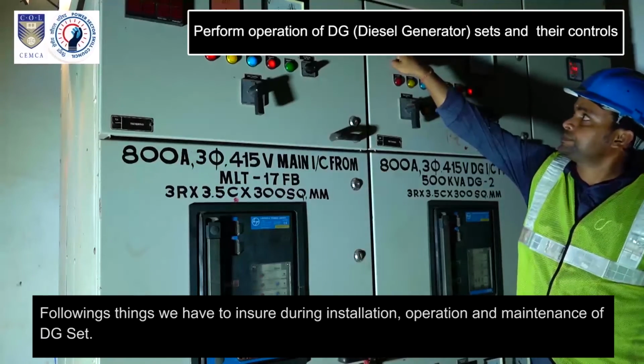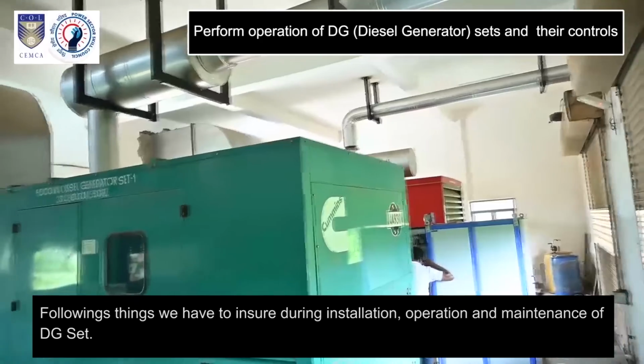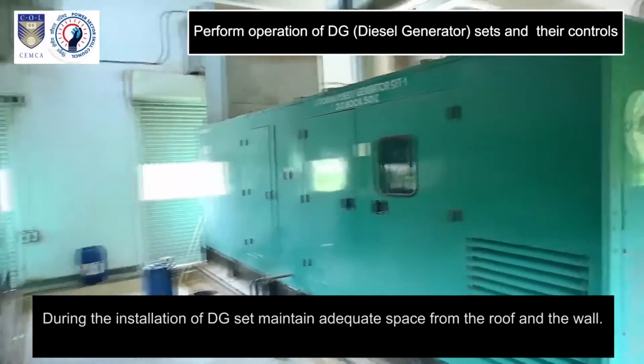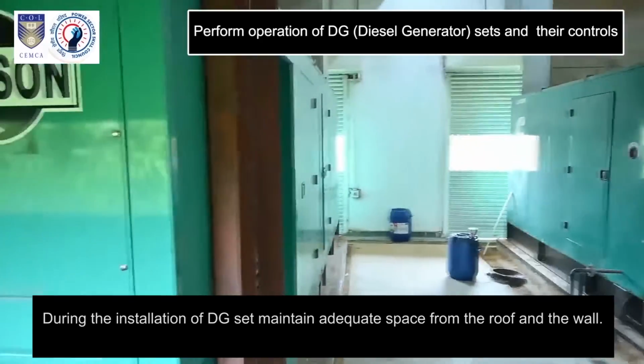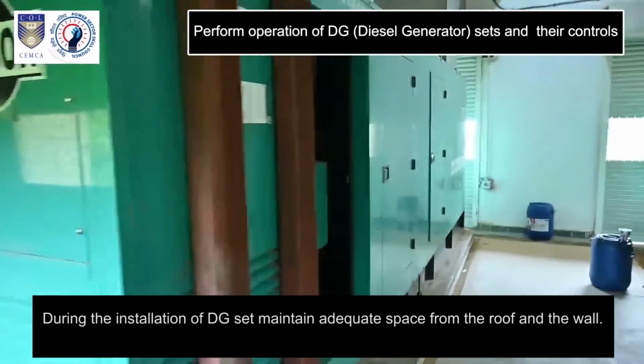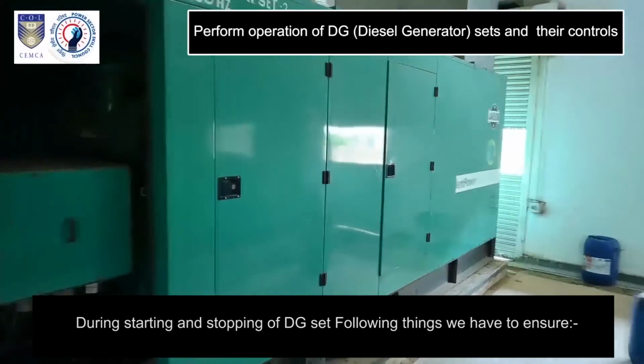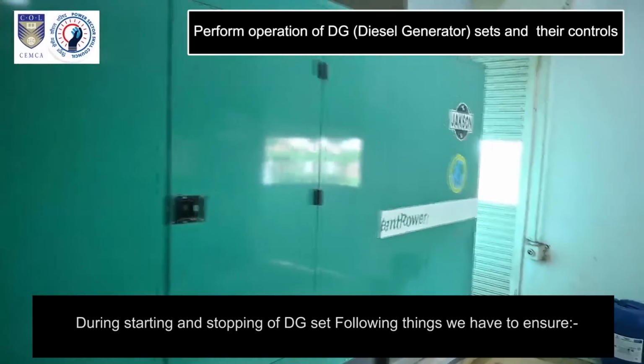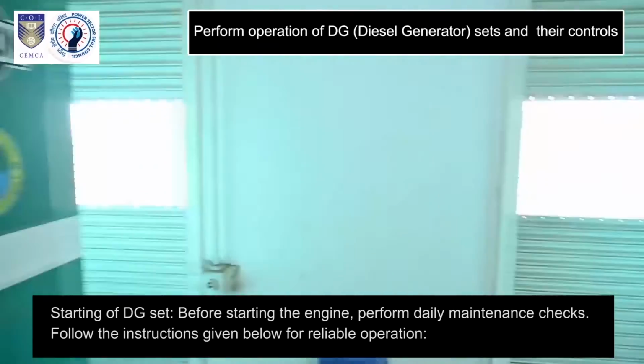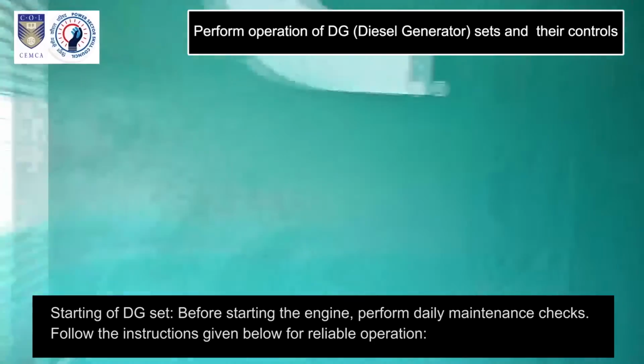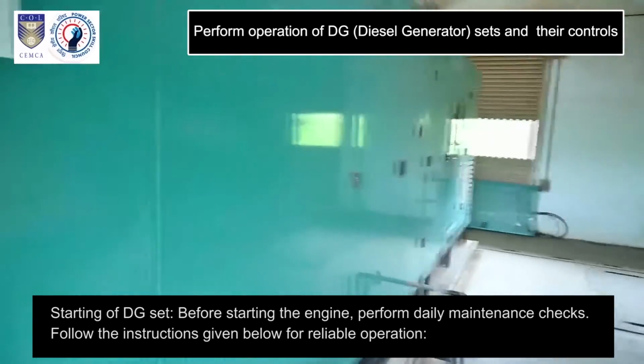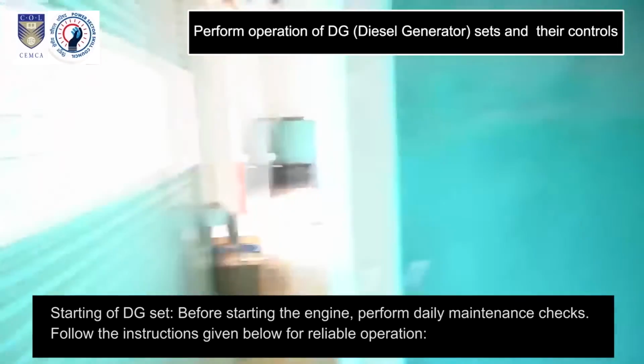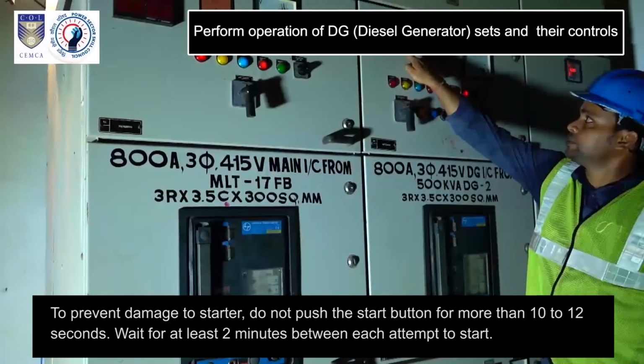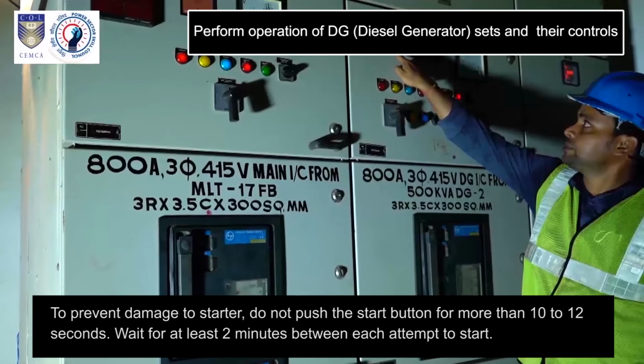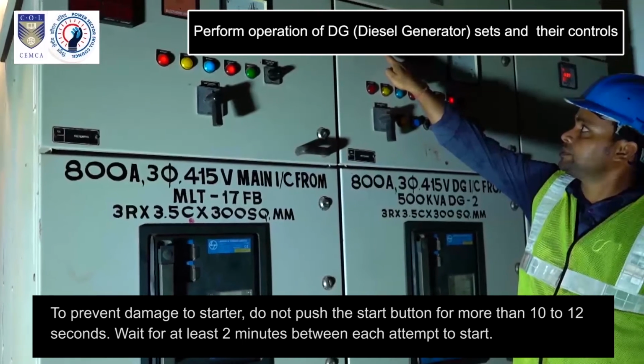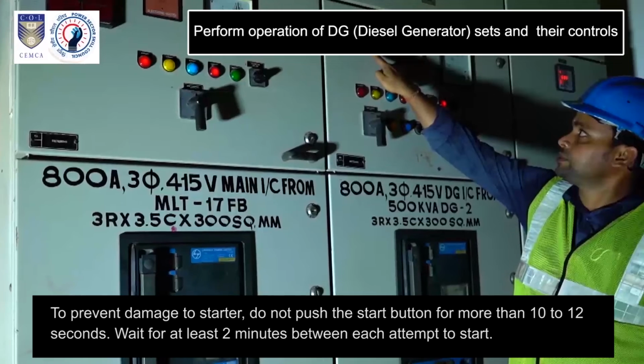We have to ensure the following things during installation, operation and maintenance of the DG set. During the installation of the DG set, maintain adequate space from the roof and the wall. During starting and stopping of the DG set, we have to ensure the following. Starting of the DG set. Before starting the engine, perform daily maintenance checks. Follow the instructions given below for reliable operation. To prevent damage to the starter, do not push the start button for more than 10 to 12 seconds. Wait for at least 2 minutes between each attempt to start.